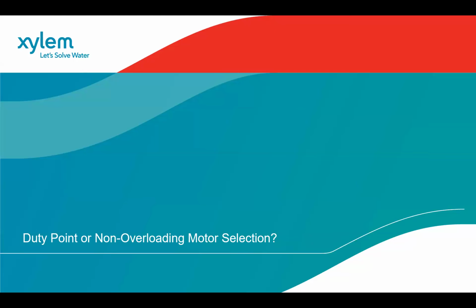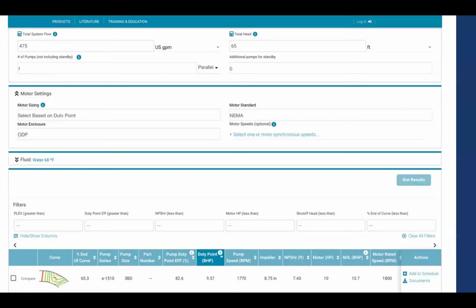Duty point or non-overloading. When you go to select a pump, you have two sets of conditions. Do I want to pick it to duty point? What is my design condition? Or do I want to pick it to non-overloading? So as we get into some software, I'm trying to select pumps and I'm typing in, hey, what's my flow rate? I need 475 gallons a minute. Through my calculations, I've established I need 65 feet of pressure differential, feet of head.